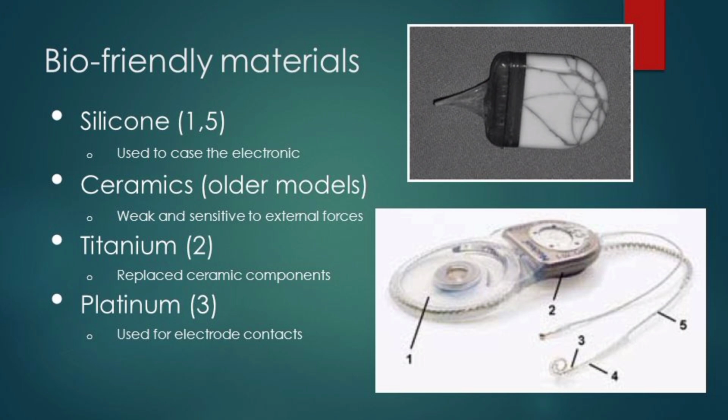For a cochlear implant, the transmitter coil should be in a silicone sheath. The electronics are enclosed in a titanium casing, and then the electrodes with platinum contacts are in a silicone array, and the cable should be of silicone type.